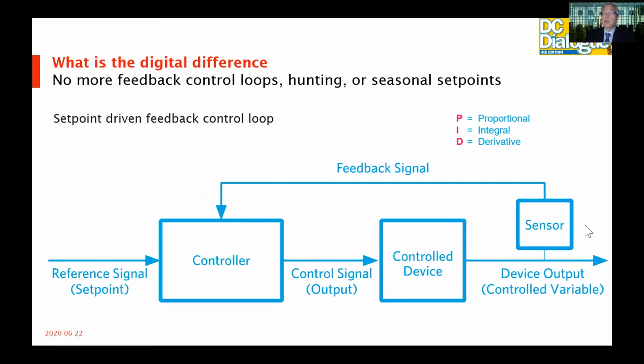And with feedback control, you have a sensor picking up the output, in our case, typically temperature. And that signal gets fed back to a controller where it's compared to a set point. And then there's an adjustment signal sent out to a controlled device, maybe a valve or a fan speed. And then the sensor monitors the change of the output. The problem and challenge with this is it's somewhat unpredictable. We're not sure what the power draw is going to be. There's no way to create a digital twin from this. And it tends to hunt a lot. It tends to overshoot the set point and go under the set point. So we get these natural transients within the system.